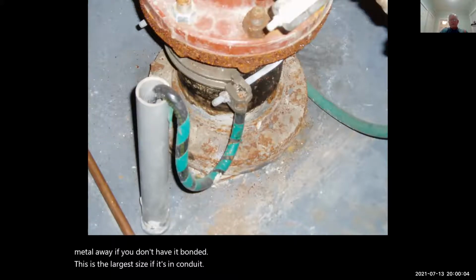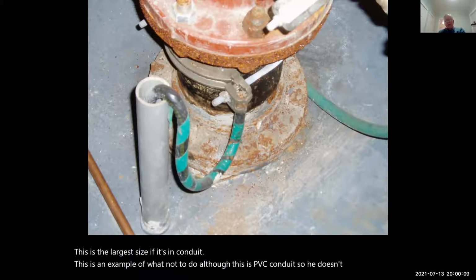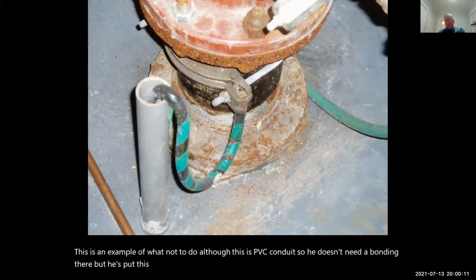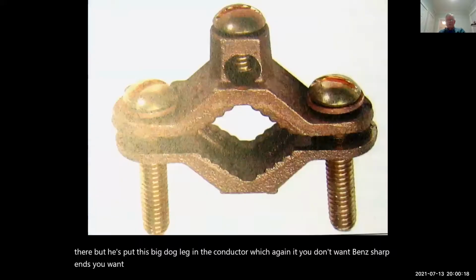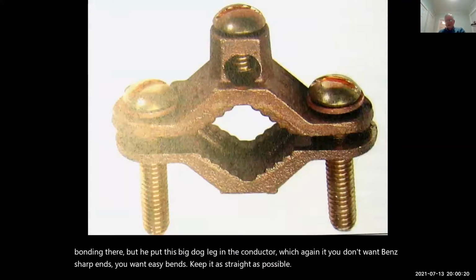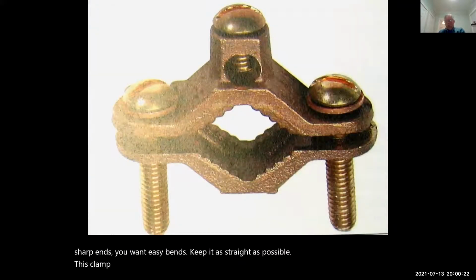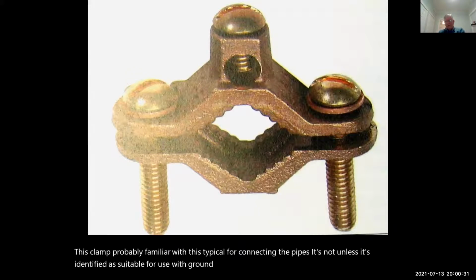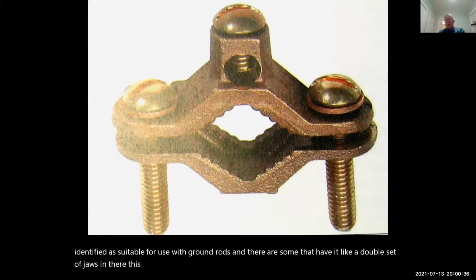This is an example of what not to do, although this is PVC conduit, so he doesn't need a bonding there, but he's put this big dog leg in the conductor, which again, you don't want sharp bends. You want easy bends, keep it as straight as possible. This clamp, you're probably familiar with, is typical for connecting to pipes. It's not suitable unless it's identified for use with ground rods. And there are some that have a double set of jaws in there. This is only for piping.